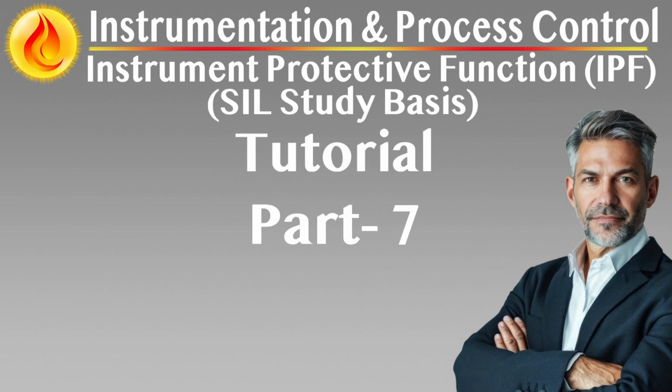Calibration and environmental compensation. Calibration frequency should be determined based on installation environment, with additional attention to dust, humidity, and background gas interference. Override management during testing. Maintenance overrides must follow strict procedures with compensating measures and clear operator notifications to avoid unprotected conditions.